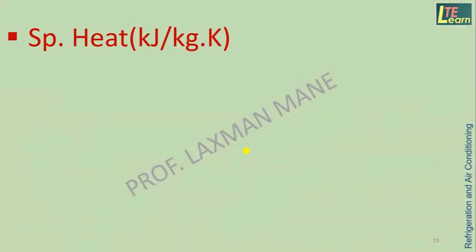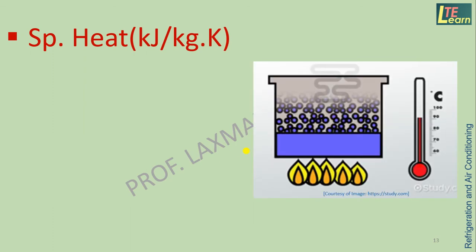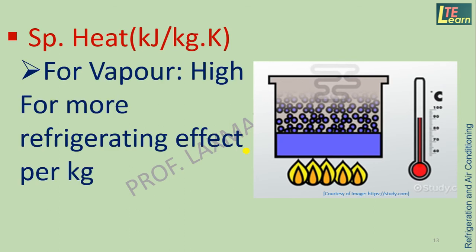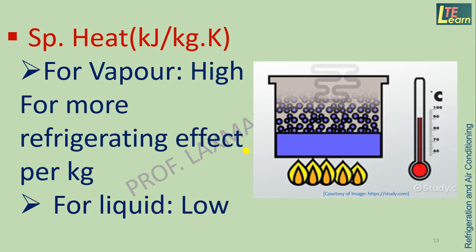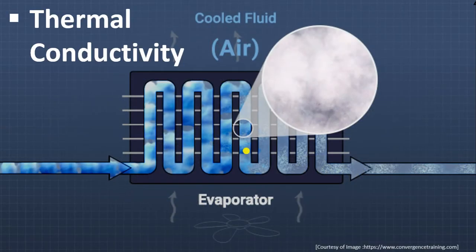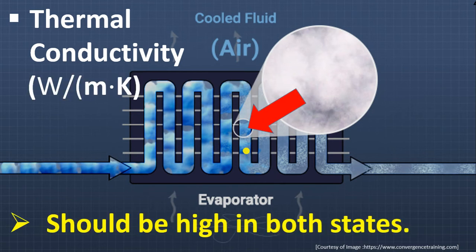Specific heat is the heat-carrying capacity of 1 kg of refrigerant per degree Celsius temperature rise. Specific heat of refrigerant vapor should be high for more refrigerating effect per kg, and it should be low for the liquid refrigerant state. Thermal conductivity — the ability of the refrigerant to carry or convey heat from the evaporator — should be high in both states: vapor and liquid.